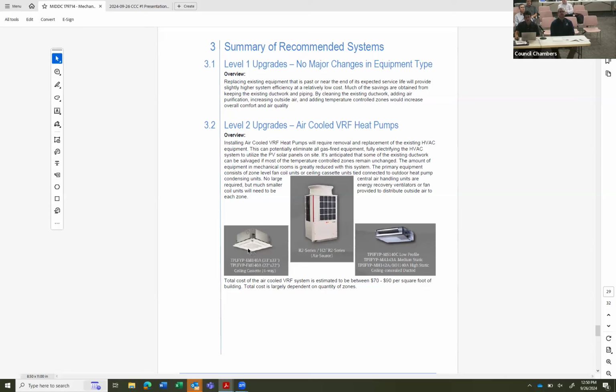an office level zoning option. The image on the left here shows an example of a ceiling cassette unit that could be provided in individual offices to provide individual temperature control. And in areas where we have more than one room per zone, we can connect it to a fan coil unit, as shown on the right here, that would be concealed above the ceiling and distributed with ductwork. And in the middle here, we have an example of the outdoor condensing unit that would be associated with these systems.